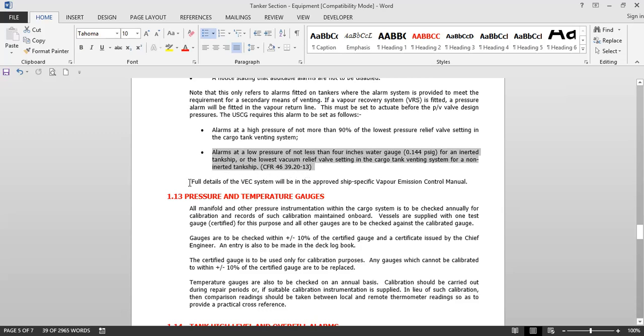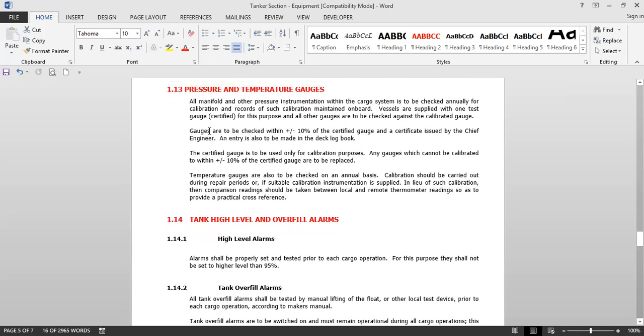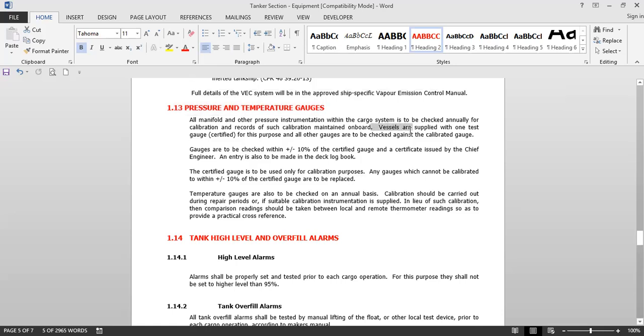Full details of a vapor emission control system will be in the approved ship-specific vapor emission control manual on board. The next equipment is pressure and temperature gauges, fitted on individual tanks. All manifold and other pressure instrumentation within the cargo system is to be checked annually for calibration and records of such calibration maintained. Vessels are supplied with one test gauge certified for this purpose and other gauges are to be checked against the calibrated gauge. Gauges are to be checked within plus or minus 10 percent of the certified gauge and a certificate issued by the chief engineer.